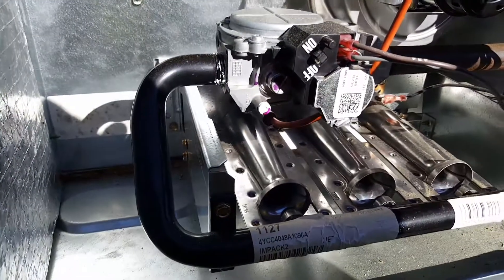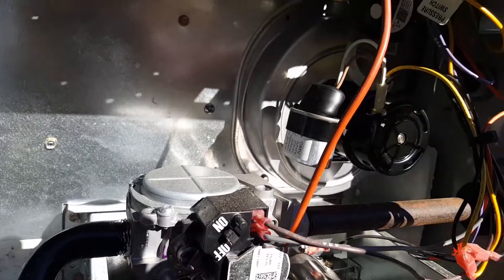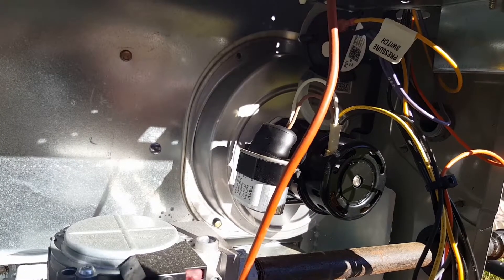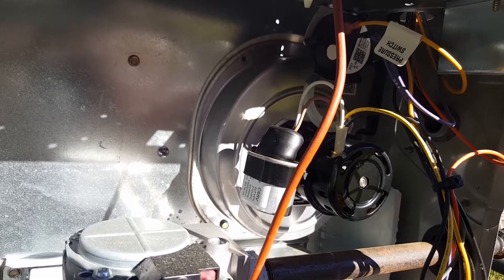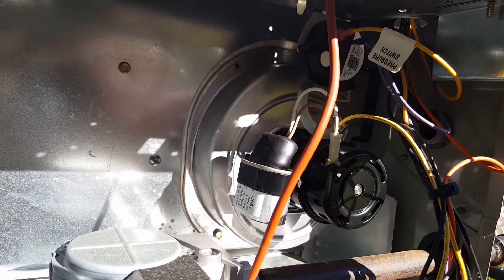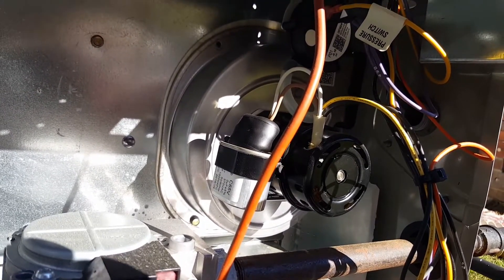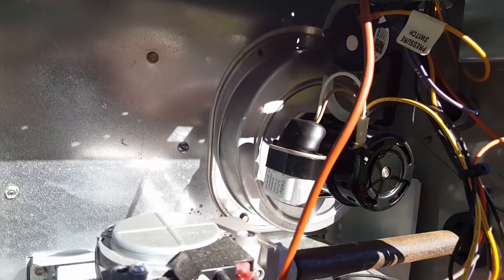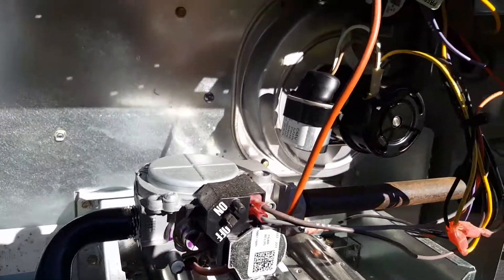I'm having calls — this is a call today on this unit, it has no heat. Yesterday, only a few blocks away, almost two years ago I installed one of these. I've already replaced the combustion blower, and they didn't have the recall out yet, so we didn't know you were supposed to drill out the bottom so the condensation wouldn't spill all over the burners.